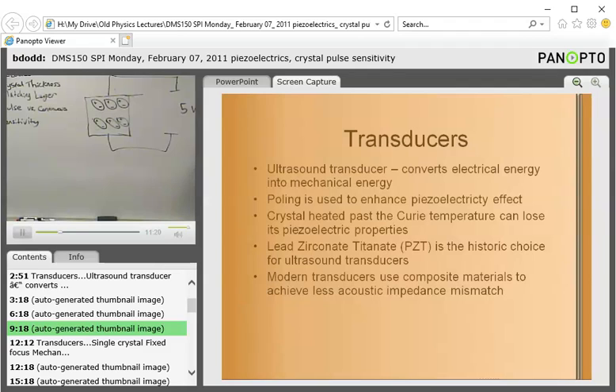Okay, so we talked last time about PZT, lead zirconate titanate, being the main ingredient of the historic choice for ultrasound transducers. That's still true. They do use some composite material in there to help reduce the matching layer effect. So it's not completely just lead zirconate titanate anymore, but there's some other stuff going on.